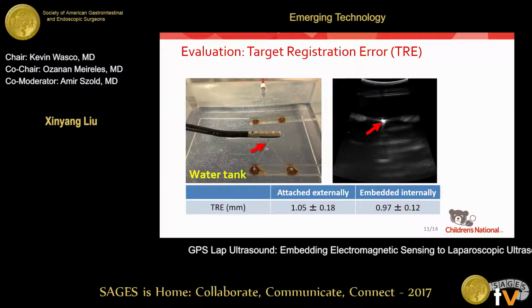As you can see, we have a crosswire phantom, and we place it in the water tank. The ground truth is the 3D location of the wire intersection, and that intersection can be obtained by touching with a needle. The needle also has an EM sensor in it, so the needle tip is tracked in real time. We place the ultrasound probe on top of the wire intersection, and we can get the intersection point in the 2D ultrasound image plane. We can transfer this intersection point to the 3D world space based on the calibration results, and we compare it with the ground truth point. As you can see, the TRE for our solution is about 1 millimeter accuracy, and it's comparable to attaching the sensor externally.